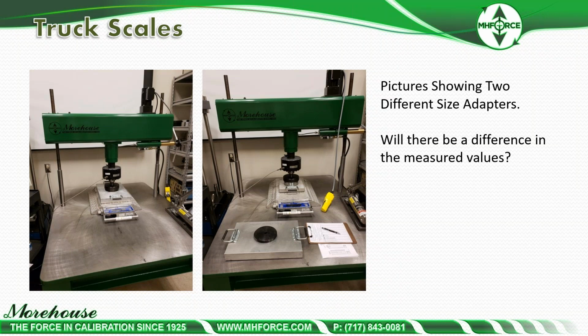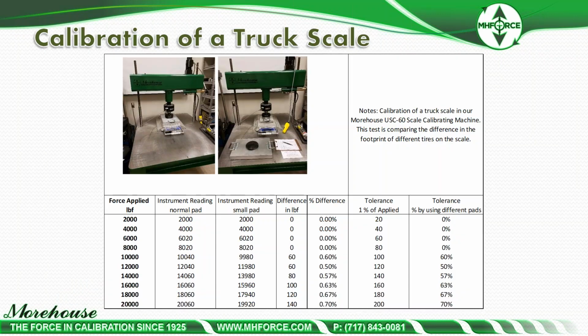When you start asking, will there be a difference in measured values? Well, here's a scenario. We had a lot of truck scales come in, about 13 of them, so I got to take a lot of different data on this, large to small adapter. If you follow me a little bit here, you can see what's going on. We have a normal pad and a small pad. The normal pad would replicate the size of the truck tire. The smaller pad was, exactly as I said, smaller. The tolerance on this was pretty wide, a 1% tolerance. But if you look at the difference of using the pads, down here we're at a 70% difference. And you can see it creeping up as you get closer and closer to capacity, where 140 pounds of that tolerance is used by switching the size of the adapter. Now, if the spec on this were 0.1% or a half percent, and we had this much change in adapters, it would not meet spec.